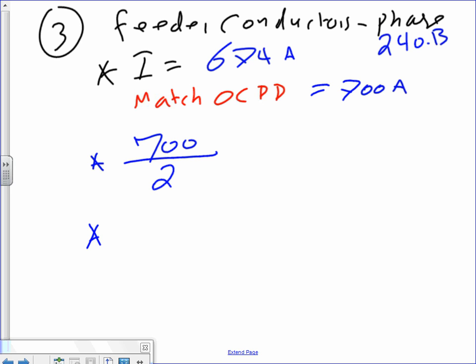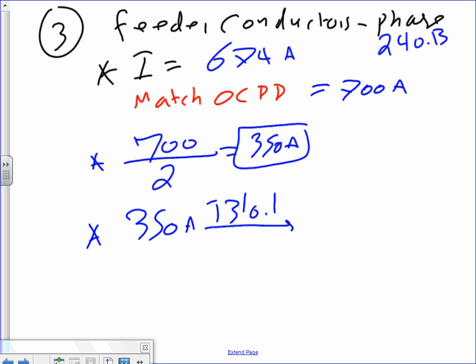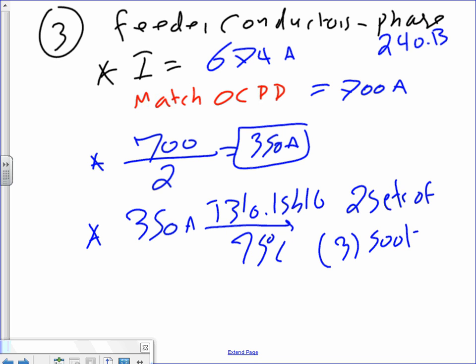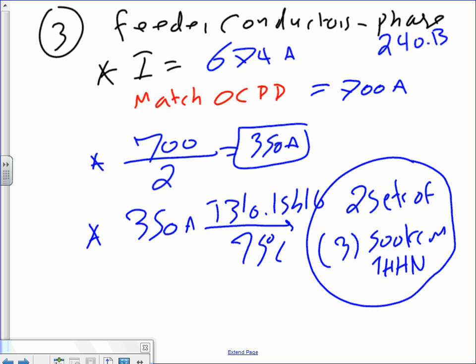So what do you do? Parallel. When you parallel, how do you start, guys? Start with 2 sets. If 2 sets doesn't give you around 400, then add a 3rd set. If you still don't get around 400, add a 4th set. If you still don't get there, you add a 5th set. So here, very clear, if I put 2, that'll get me 350. This is around 400. Then, gentlemen, I take the 350 and take it to table 310.15(B)(16) under the 75-degree column. This will give you 2 sets of 3 conductors, 500 kcmil THHN. Done. Here's the size of the feeder that's going to your lighting panel.